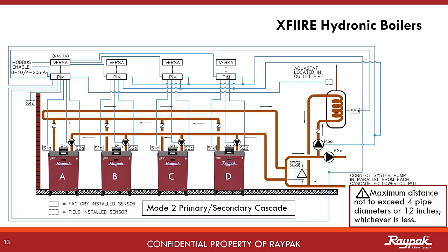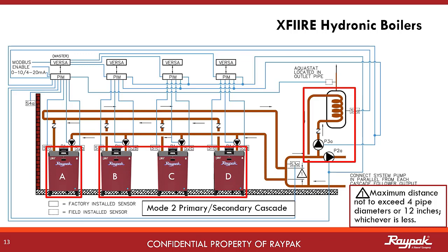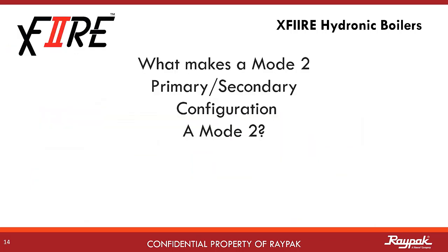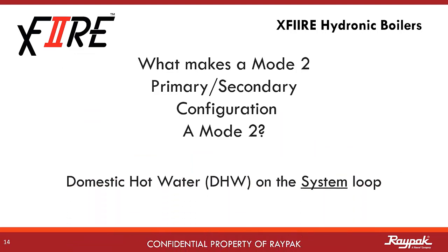Mode 2 is also possible in cascade. As with the single boiler system, the indirect domestic hot water tank is out on the system loop. When in cascade, there can be only one master boiler — the A boiler. The other boilers are the follower boilers. Always apply reverse-return logic to plumbing cascade systems: the first boiler to supply water to the system is the last on the return line from the system. What makes a Mode 2 primary-secondary a Mode 2? You have an indirect domestic hot water tank out on the system loop.